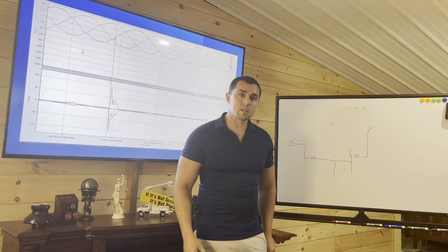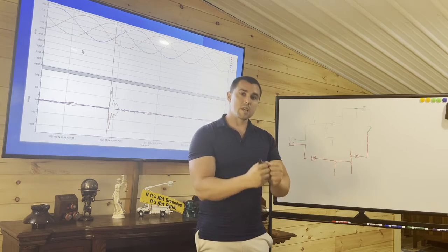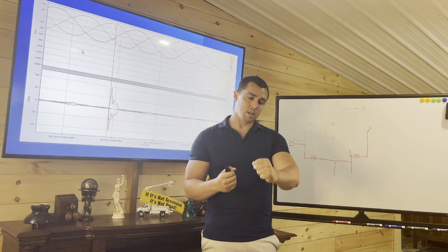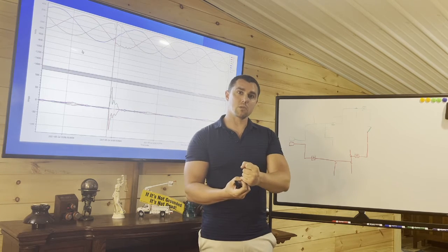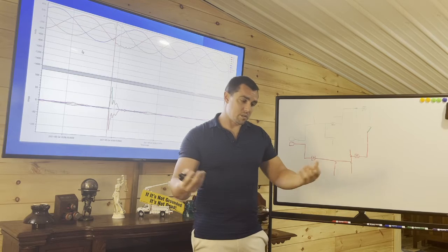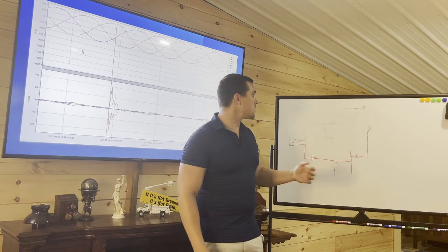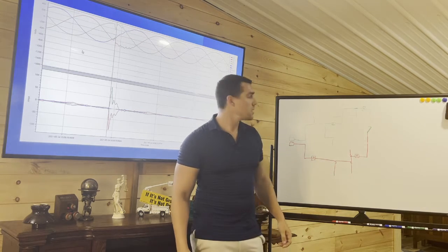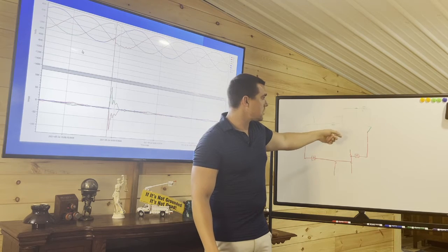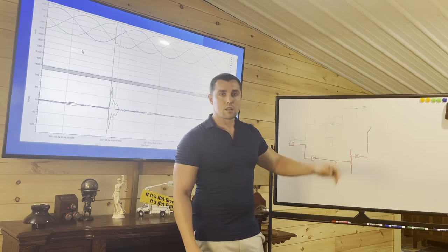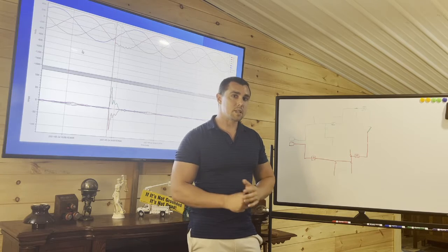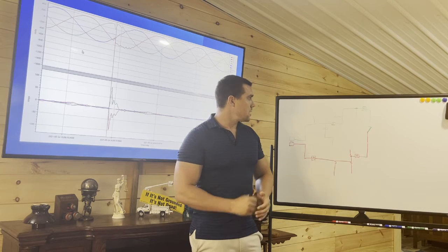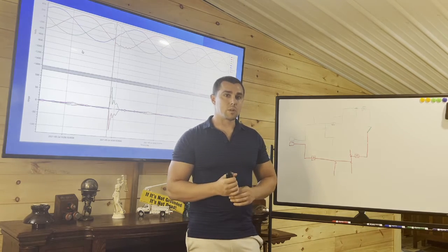So a hot energized line will actually melt the sand, create an insulator, and that sand will actually form glass around the conductor, and it'll just sit there alive because there's not enough fault current at the end of the line. Once you start changing your configuration like this, and however many times they change, it's a nightmare to coordinate.